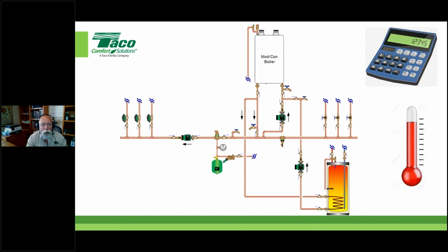That boiler supply temperature, this is a review. We've done this before with you. This is just a little showing you, if I had a 140-degree temperature going out to the system and I designed it at a 20-degree delta T, that shows me my delta T across the system. The question is, what should I set the boiler up for so that I get this 140-degree out here when I actually have a blending happening here? It's actually higher than 140. How do we know how to figure out what it is?